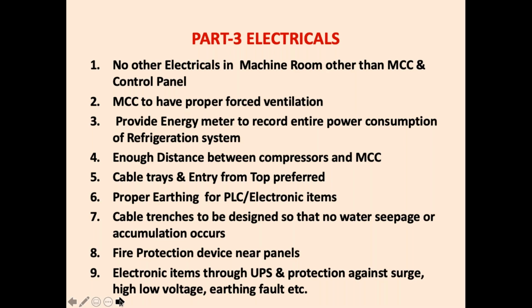Proper earthing is very, very essential. In a lot of places we get complaints that the quality of solenoid valves is not good, that coils are constantly burning. I said, "Put in imported ones and see." After that, it started happening with them also. Then I said your earthing is not proper. Your earthing is faulty. Do proper earthing and these problems will be overcome.